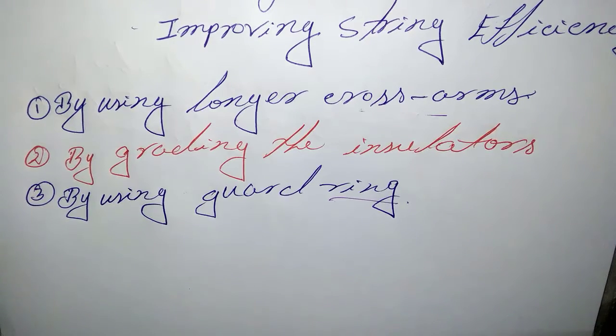K is the ratio of shunt capacitance to mutual capacitance. The lesser the value of K, the greater is the string efficiency and more uniform the voltage distribution. The value of K can be decreased by reducing the shunt capacitance.